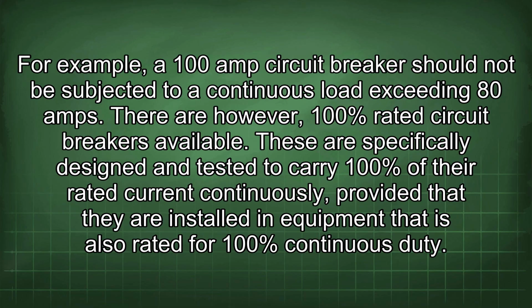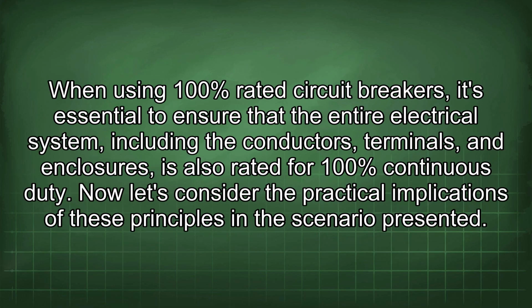There are, however, 100% rated circuit breakers available. These are specifically designed and tested to carry 100% of their rated current continuously, provided that they are installed in equipment that is also rated for 100% continuous duty. When using 100% rated circuit breakers, it's essential to ensure that the entire electrical system, including the conductors, terminals, and enclosures, is also rated for 100% continuous duty.